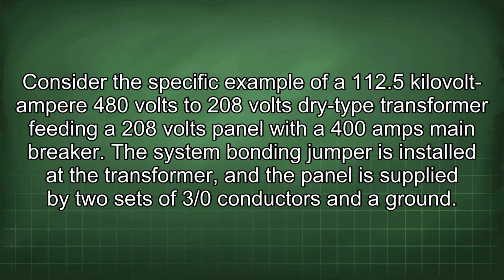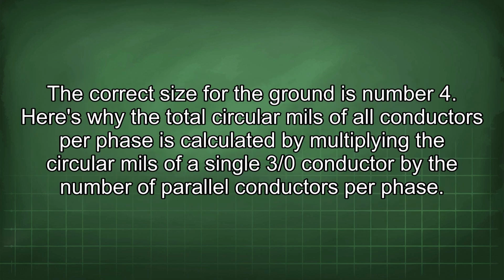phase. Consider the specific example of a 112.5 kVA, 480 volts to 208 volts dry type transformer feeding a 208 volts panel with a 400 amps main breaker. The system bonding jumper is installed at the transformer, and the panel is supplied by two sets of 3/0 conductors and a ground. The correct size for the ground is number 4.